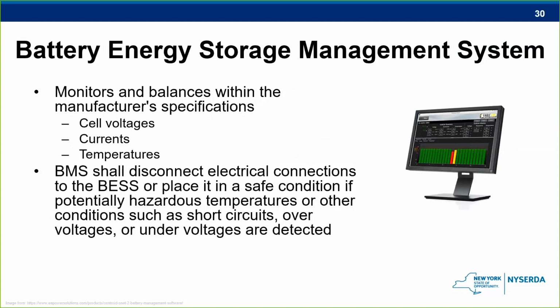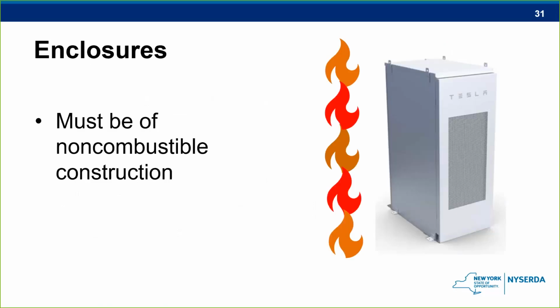And we touched on this briefly earlier, but the battery management system is really an instrumental safety feature for energy storage. You can think of it as the eyes and ears, maybe even the brains of the battery system's health. It's constantly monitoring the state of health of the energy storage system and responding accordingly. For example, it might detect an individual cell overheating and shut it down and isolate it from others to prevent thermal runaway from occurring. So you can imagine if the battery management system were to fail, the system would lose a major safety feature, which is why those UL listings, test protocols, and commissioning are so important.